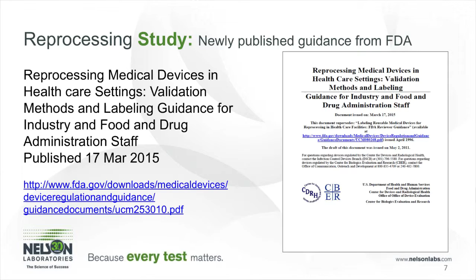The most recent and important guidance for reprocessing for medical device manufacturers is the new guidance from the FDA. This is from a draft version from 2011, and it is their new version that just came out just a couple weeks ago. The major differences are the Appendix E, which specifies devices in which a 510(k) should contain data to validate reprocessing instructions, as well as the fact that 2 quantitative markers should be utilized for the cleaning validation and definitions of controls that are utilized in the validations. But this is a very key document for medical device manufacturers. And the FDA has been utilizing the information in this document since before 2011.